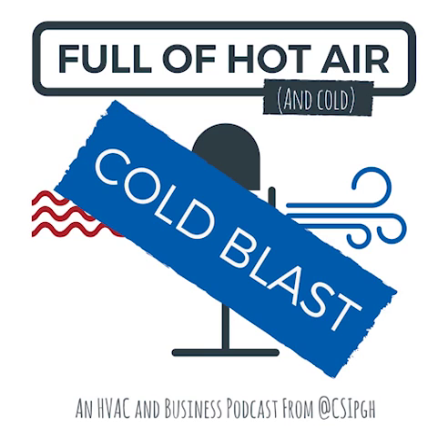So we want to take the actual voltage that's coming into the heater section in that air handler. Let's use a basic example, 240 volts. You'll very rarely see 240 volts right on the money, as most techs know, but we'll use that for the example. Say we have 240 volts and our amp draw is 60 amps. That comes out to 14,400 watts, which is basically where you get your 15 kW. Then we want to turn that into BTUs, because our formula requires BTUs, not watts.